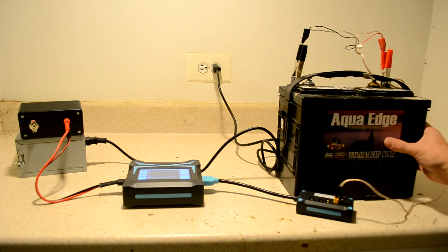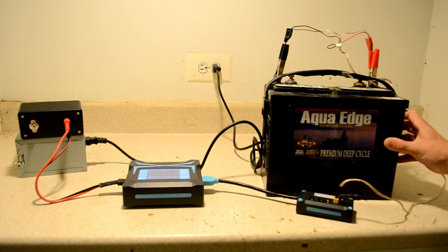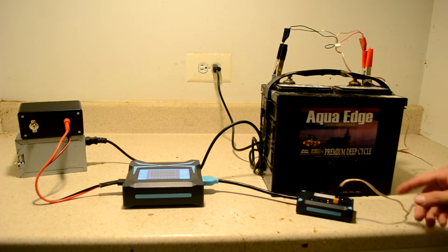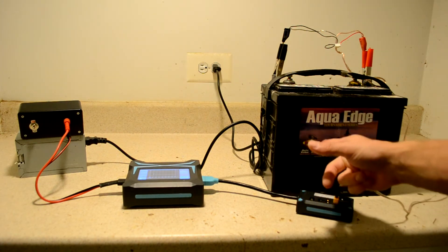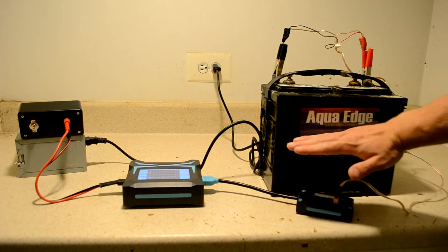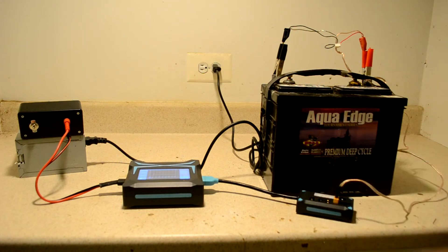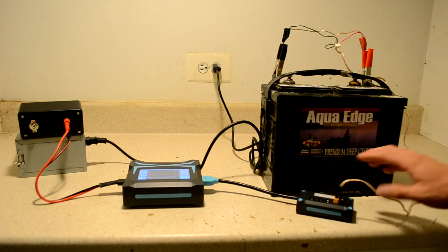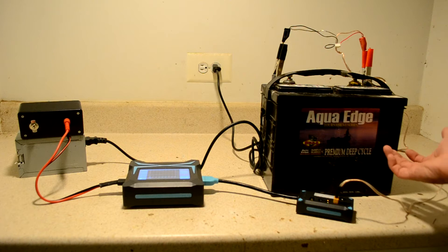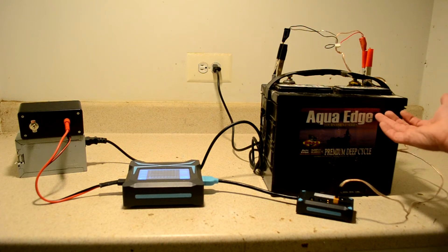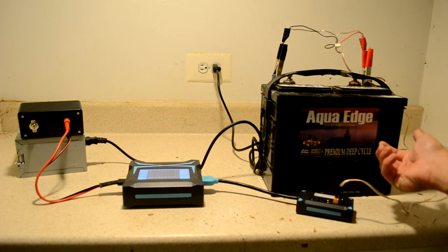This battery, and if I shake it, you can almost hear it sloshing around. Inside this battery, there are multiple plates of lead submerged in sulfuric acid. And one of the things that you have to do frequently is top up the water level in there, dilute the sulfuric acid a little bit to make sure that none of the plates are exposed.